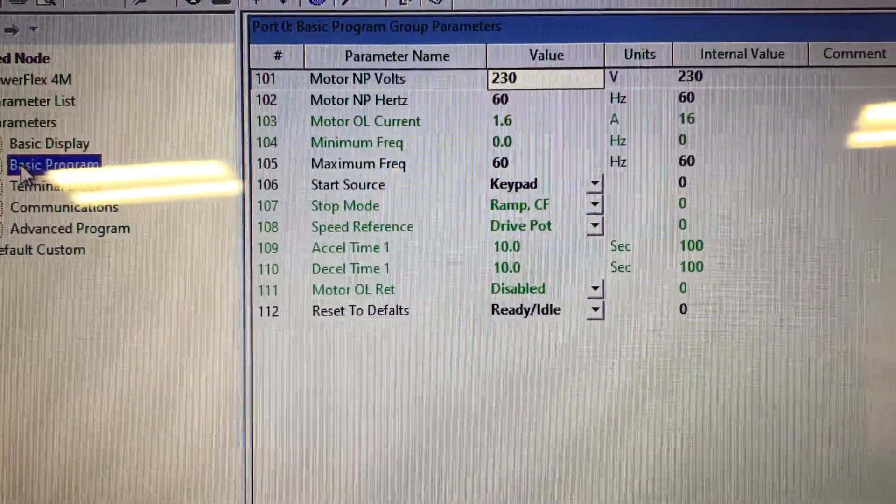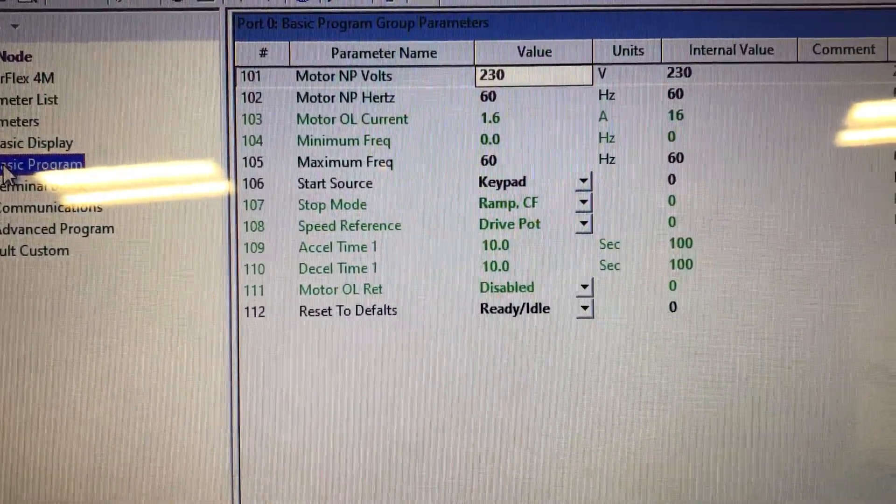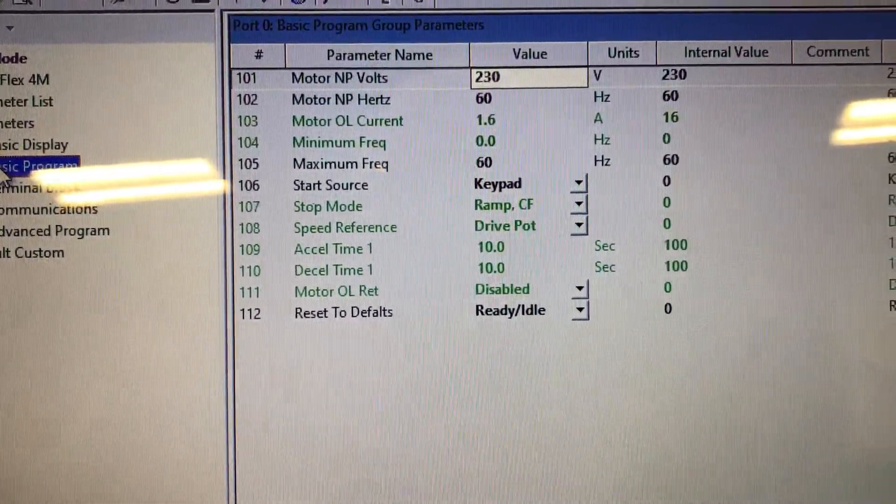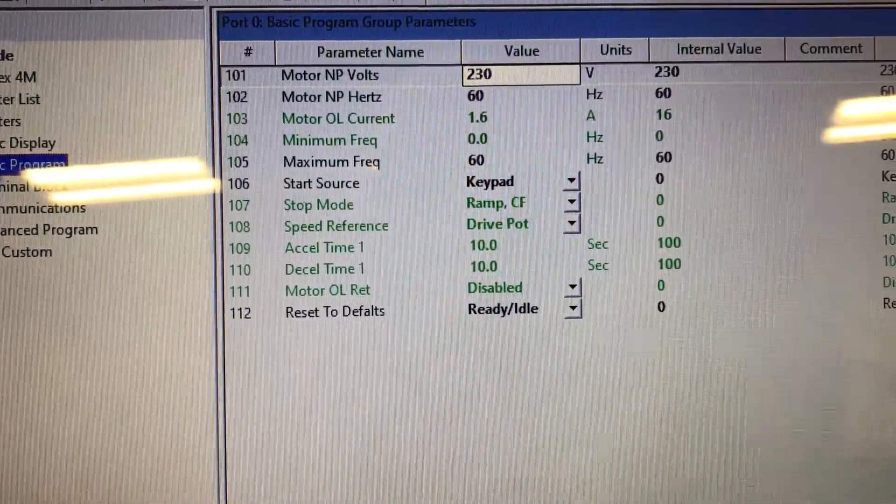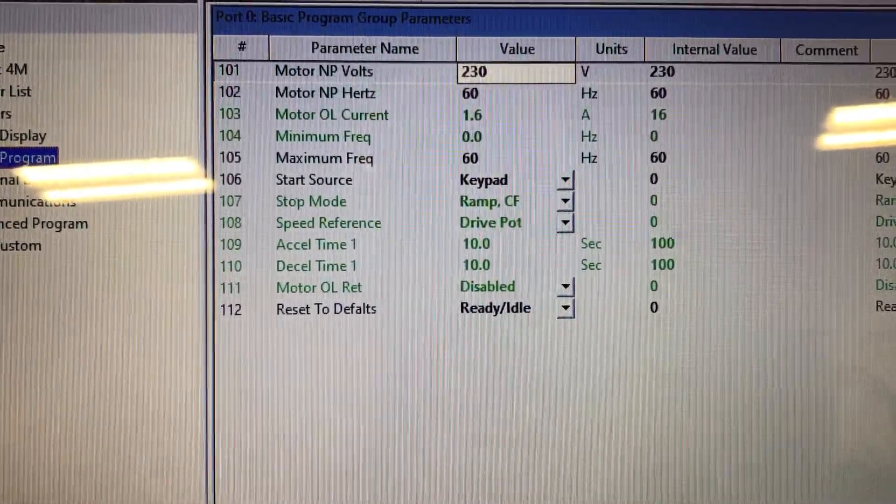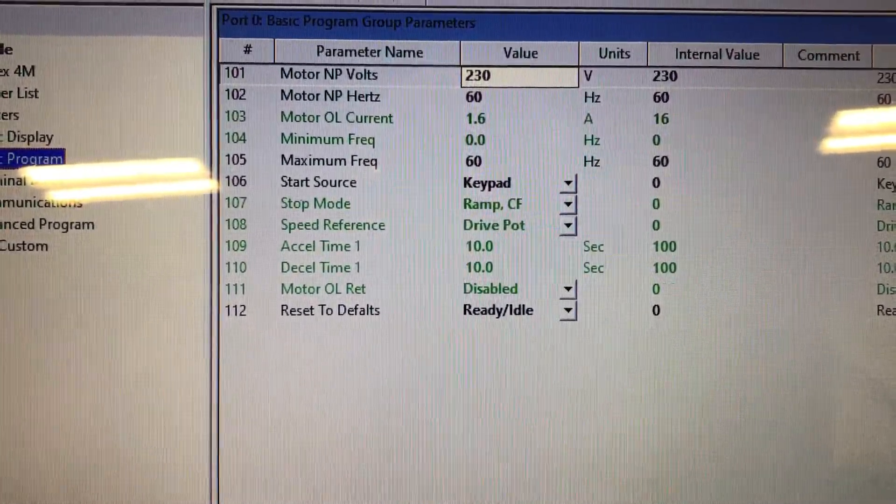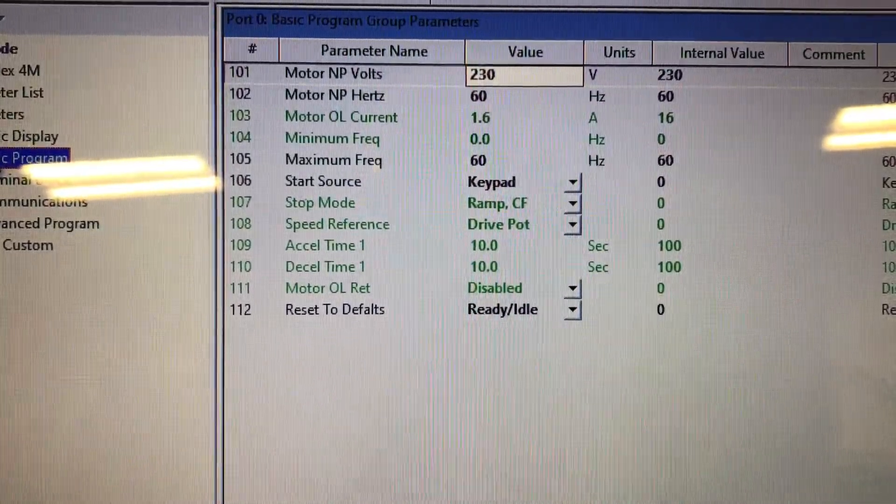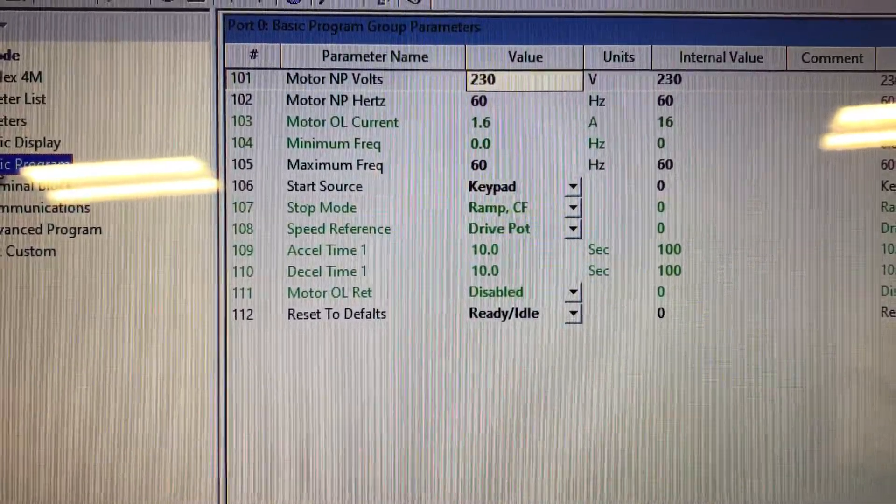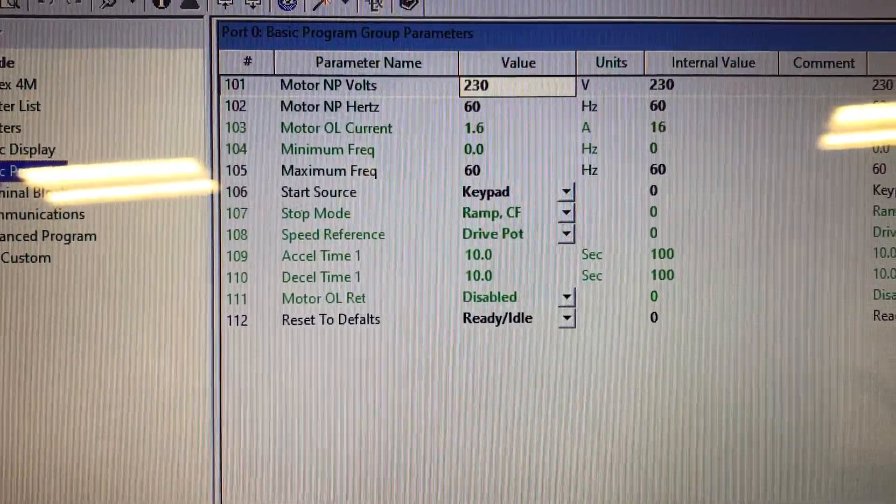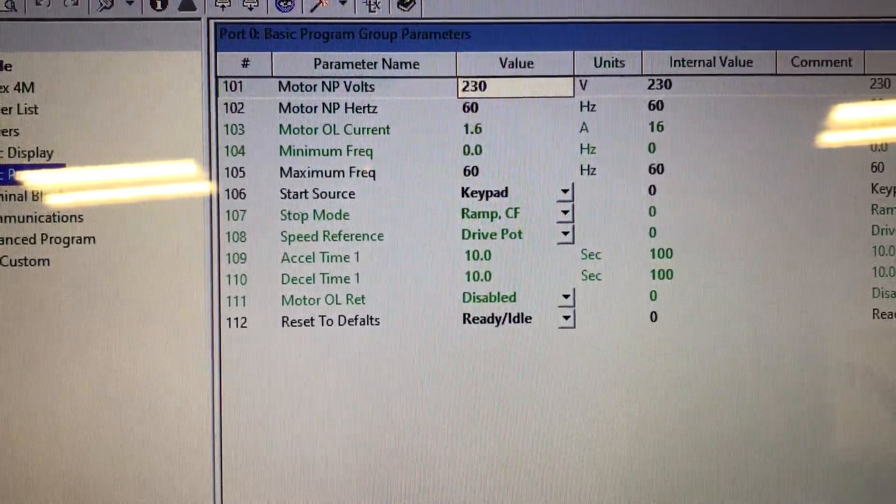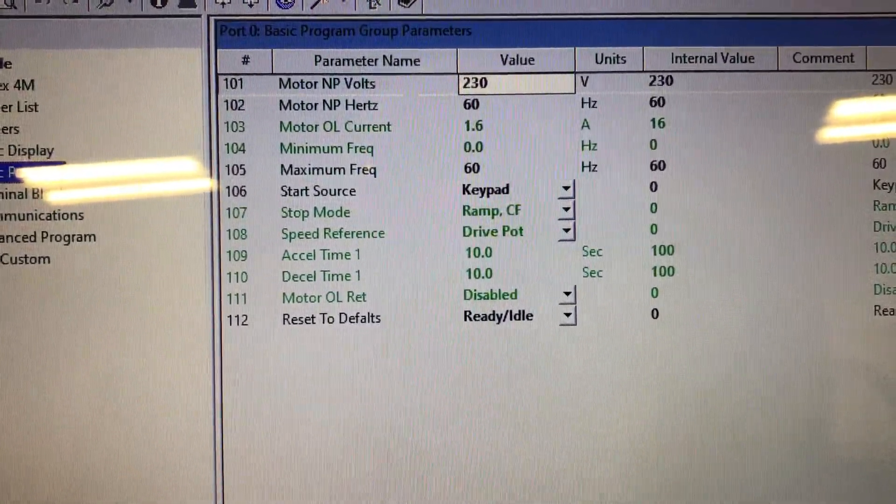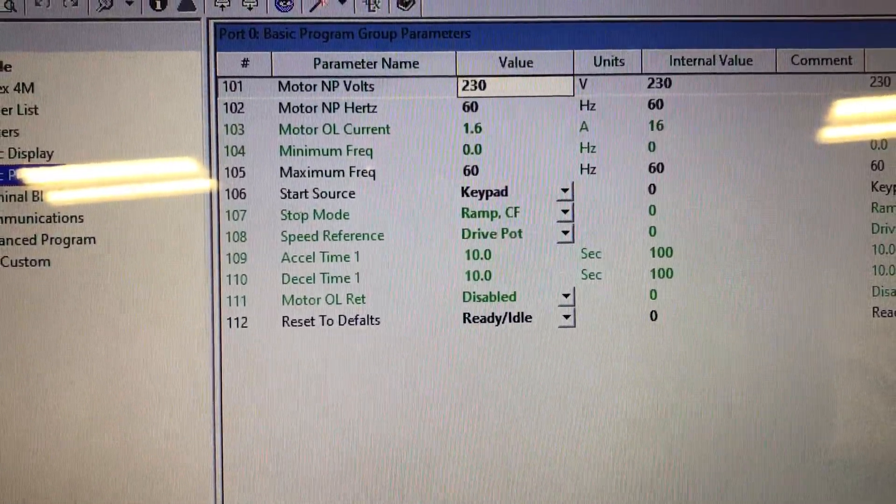Accel time and decel time, that's what the ramp is going on. So in our case, our accel time is 10 seconds, which means if you push the start button and you had 60 hertz in there, it would go from zero to 60 in 10 seconds.